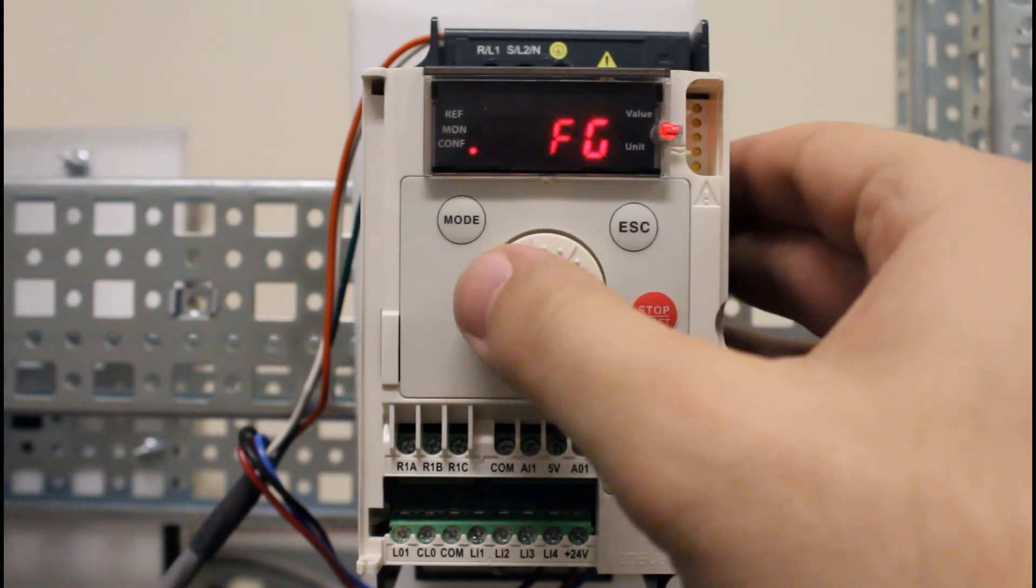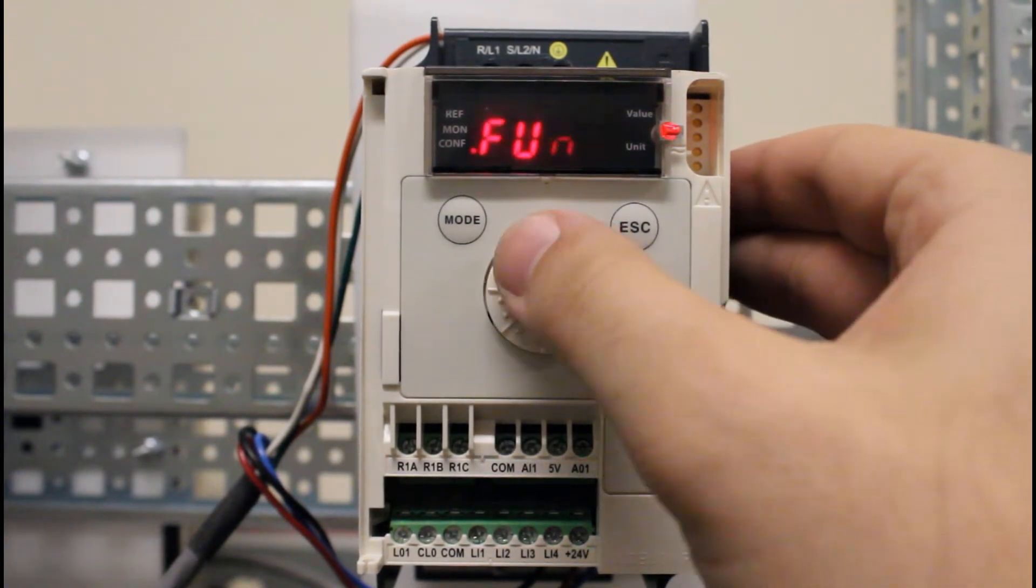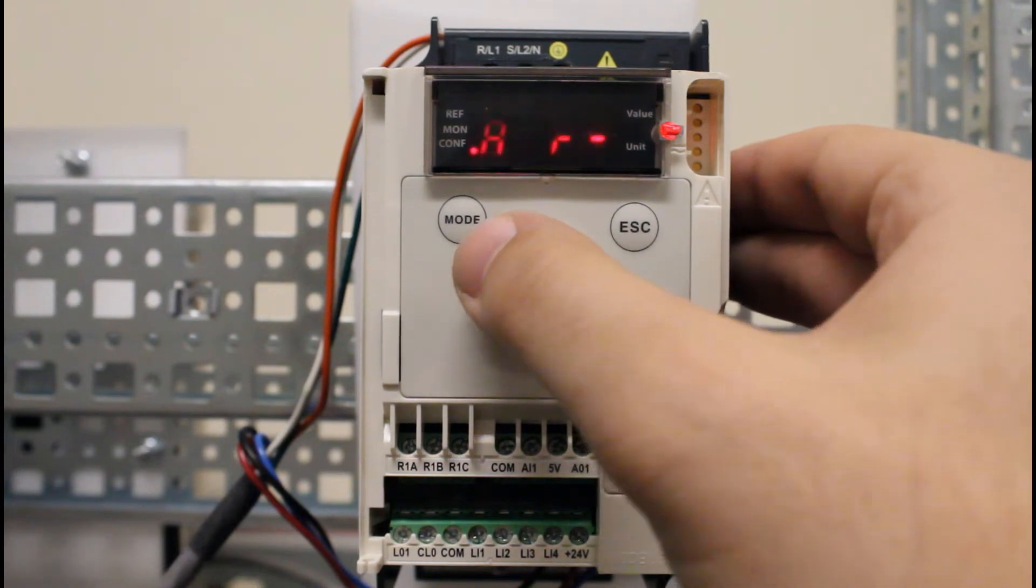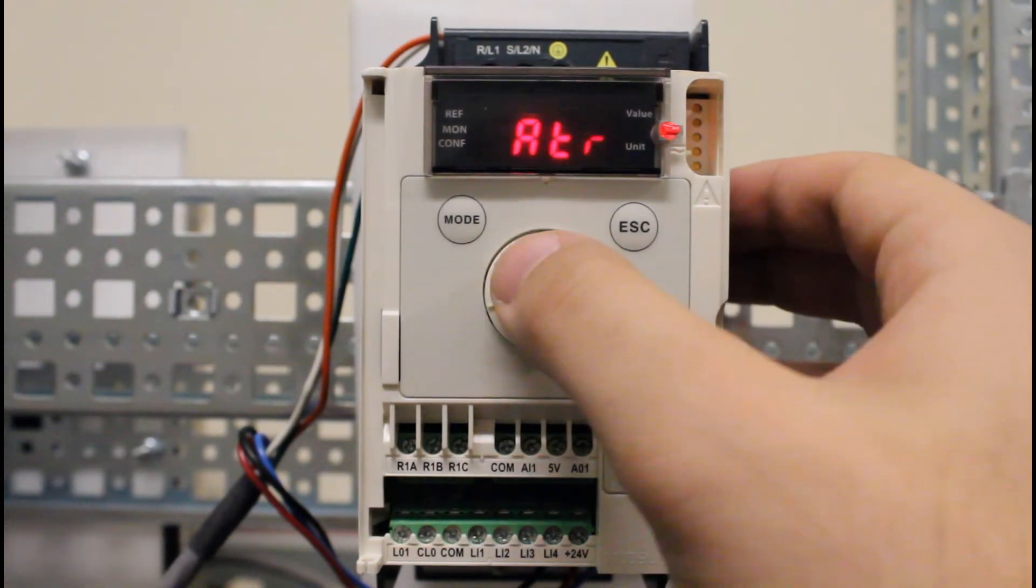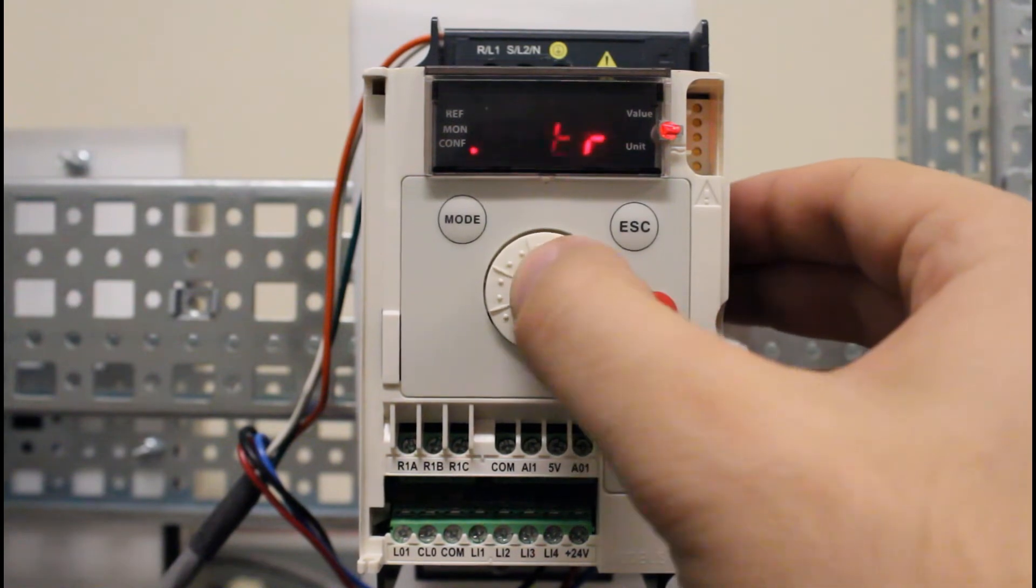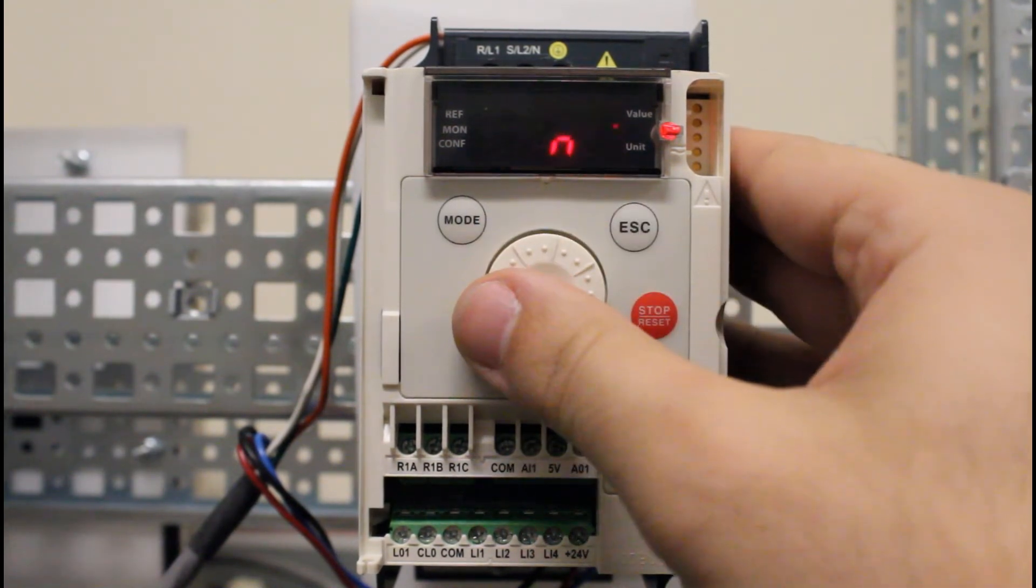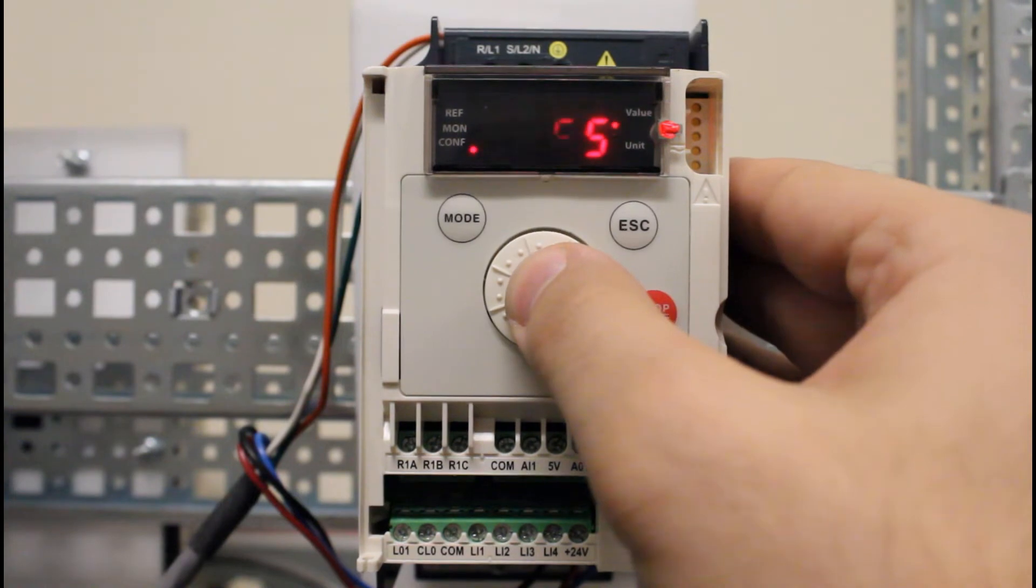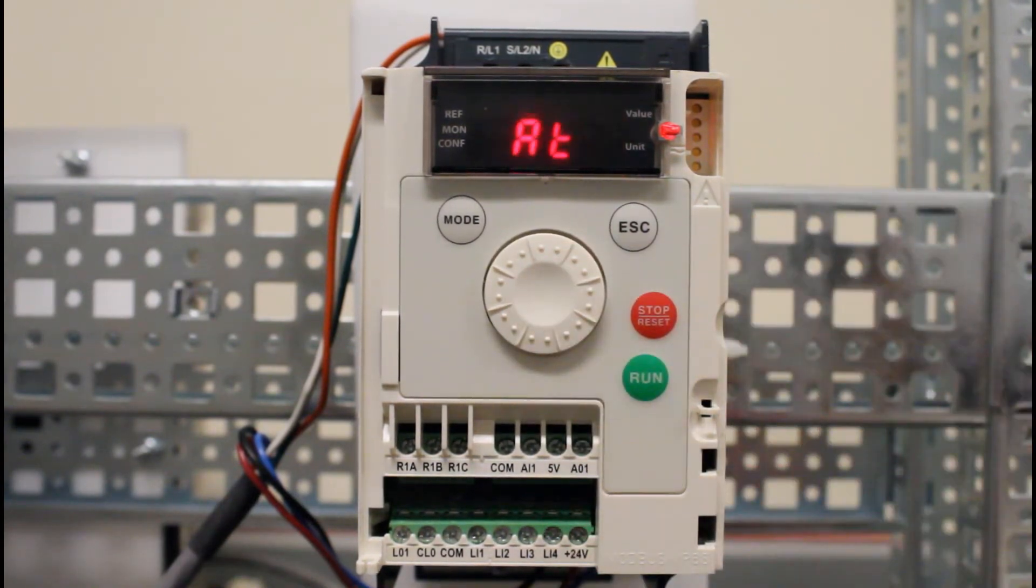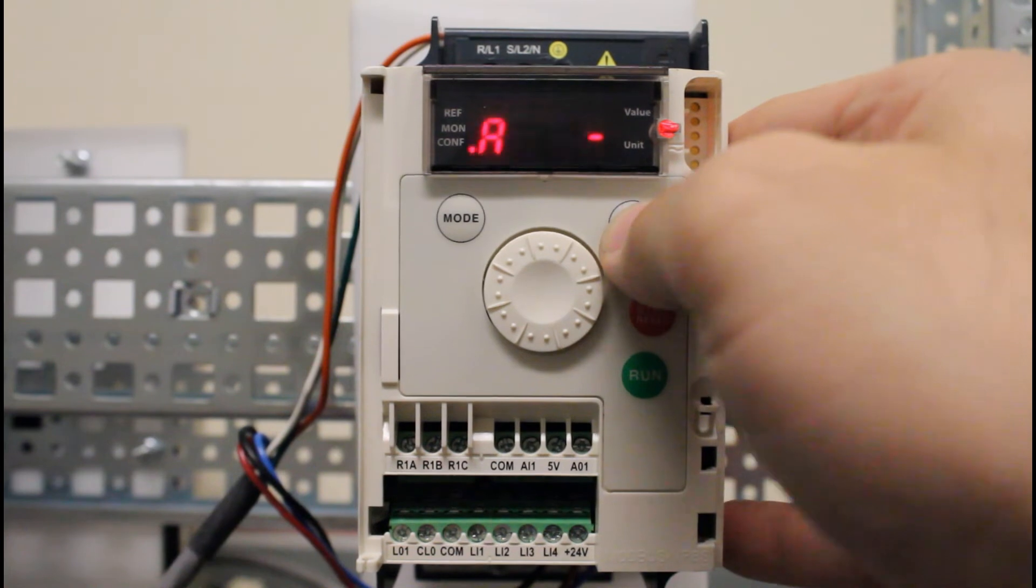Go down to the fault menu FLT dash, and here you'll find ATR - that is your automatic restart function. Press enter again here. From the default it's NO, but you can make it YES. Make sure you enter to save it, and it'll go back to ATR.